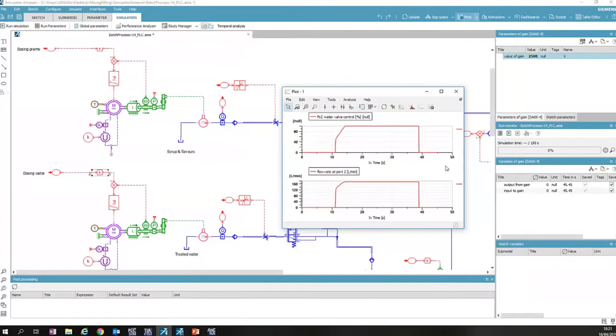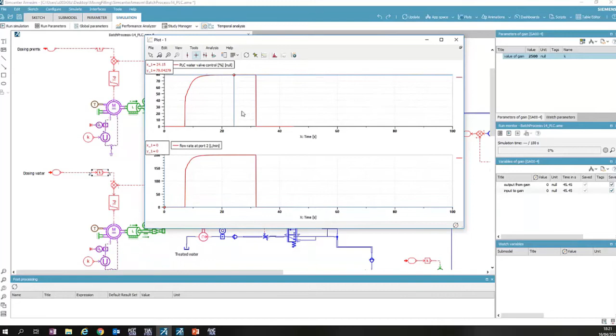the control is now done properly, and we're reaching the 200 liter per minute set point. I can also go back to Simcenter Amesim and plot the results. As you can see, the PID control on the regulating valve is opening the valve to 80%, and we are reaching the set point that was set by the PLC for this recipe: 200 liters per minute. So this was a small example of how you can use this software-in-the-loop setup to track issues that might be coming from the design of the system or from the automation control.